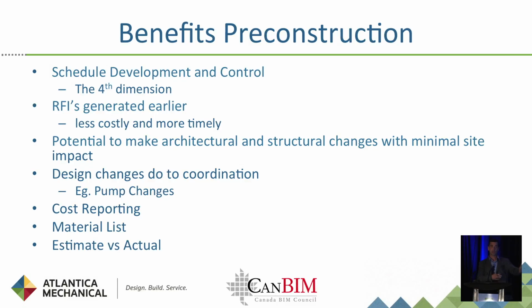So what we can do as a contractor that understands constructability is produce that domestic water system true to form and provide it back to the engineer or design engineer, and they can actually rerun their calculations. If we do it in Revit, they really only have to push a button that will tell them the net suction head and all the other things they're concerned about, which allows them to resize that pump or pick a different pump model, with energy management and continued operation implications. There's a lot of implications we can address doing virtual pre-construction.